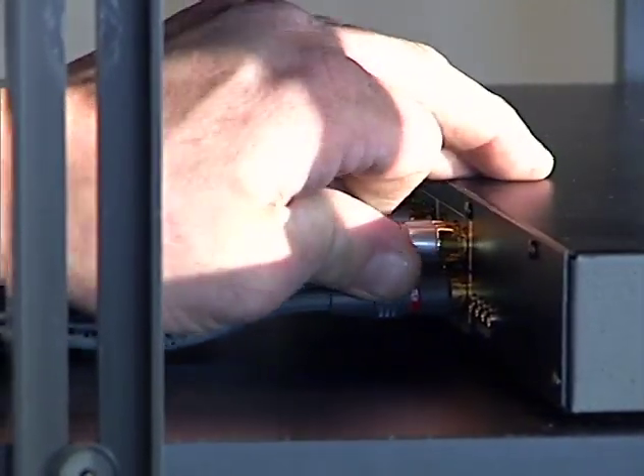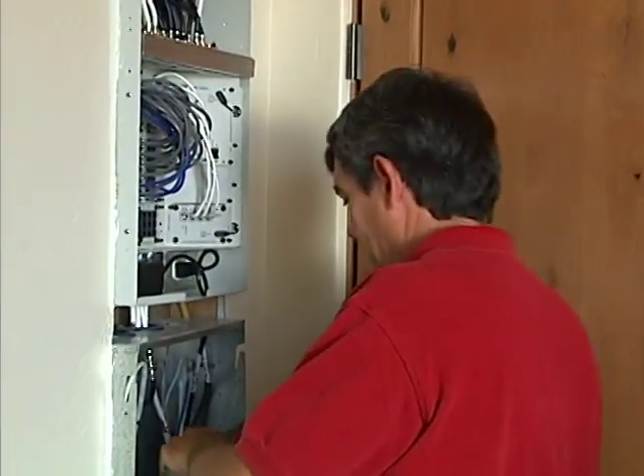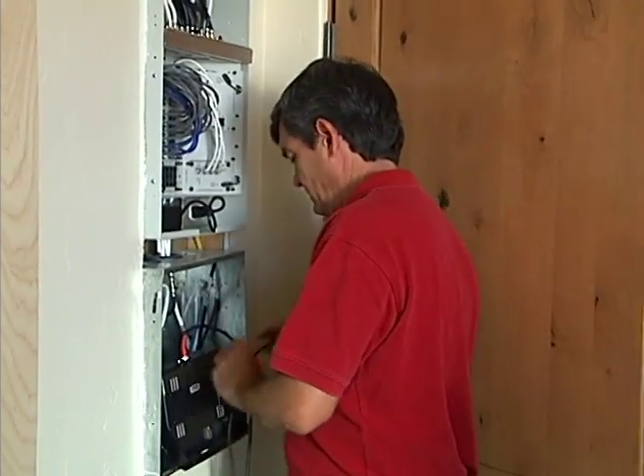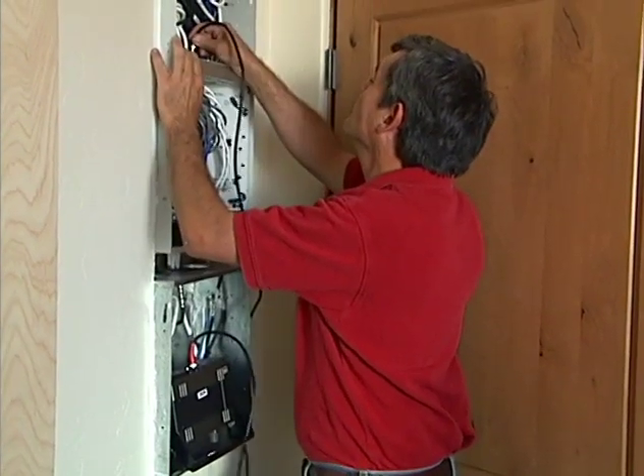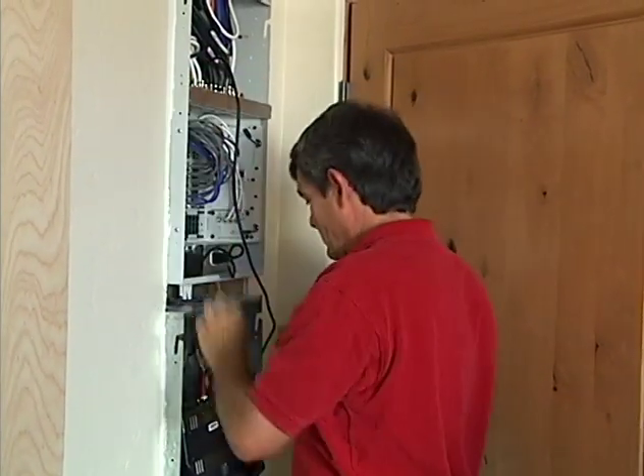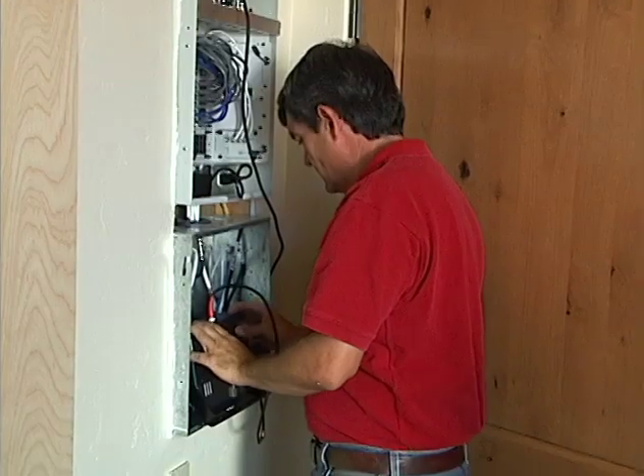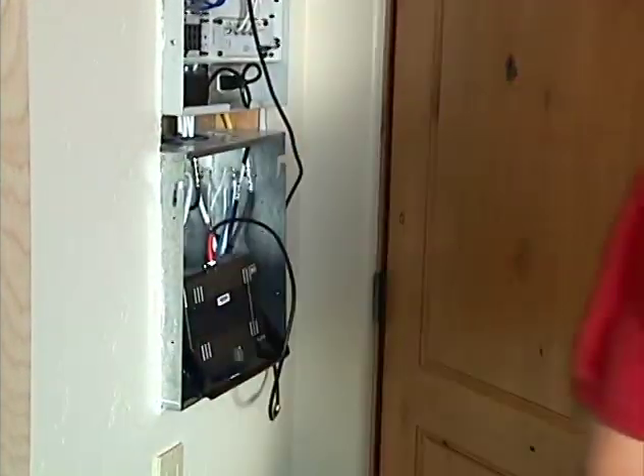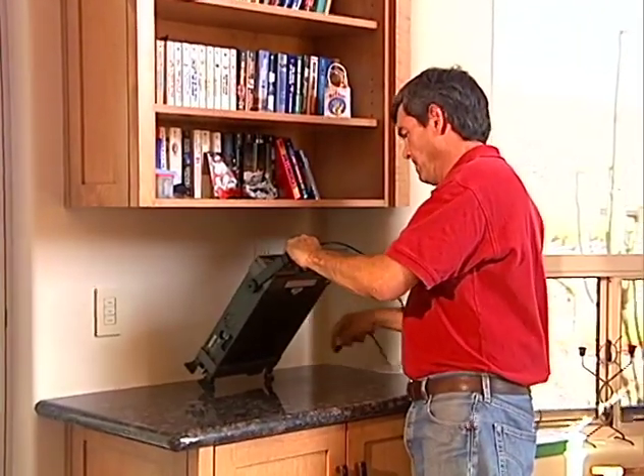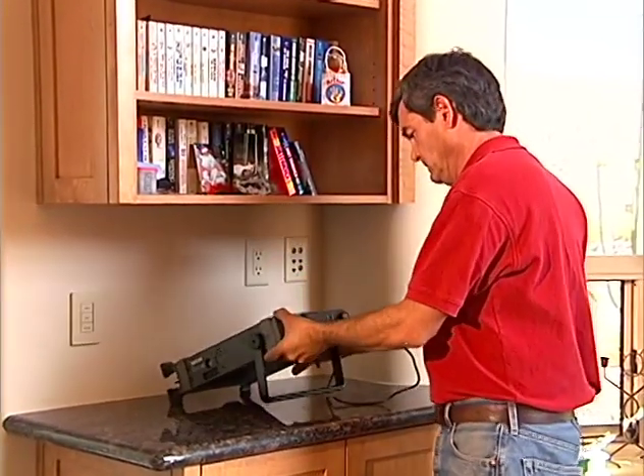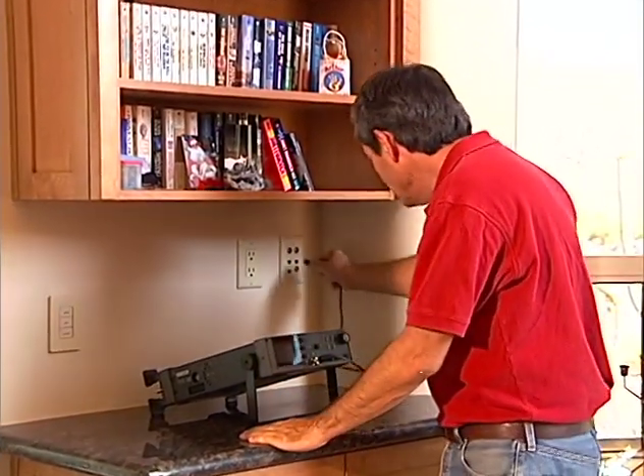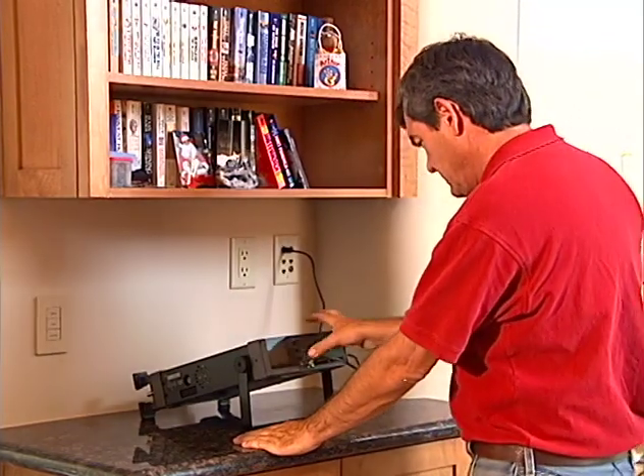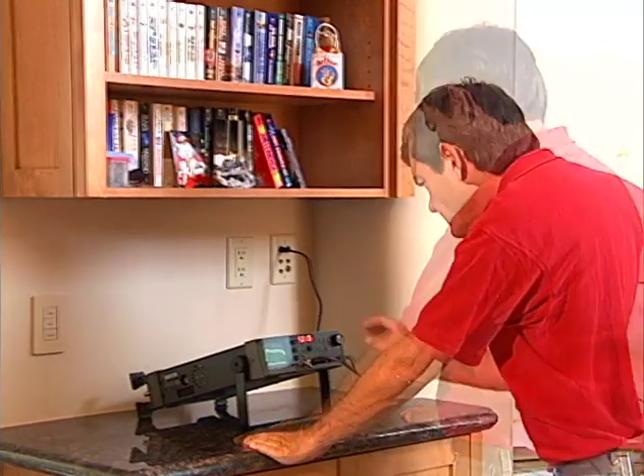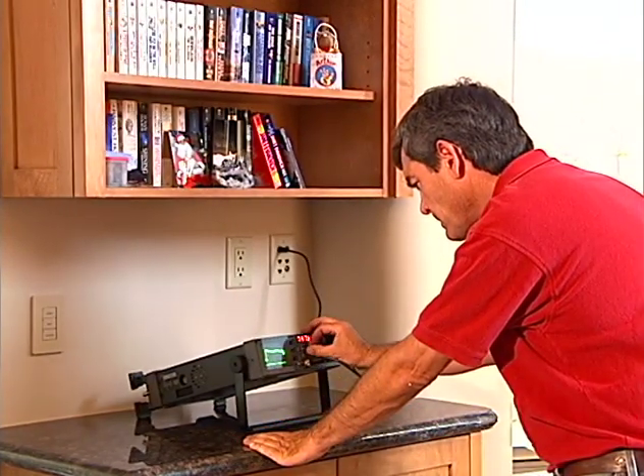While they're finishing the entertainment center, I prepare to do a final performance check of the RF distribution system. I attach a broadband RF noise generator to the off-air input without the filter and set the output level to 0 dBmV. I attach the spectrum analyzer at the outlet with the worst case loss, and set the analyzer to display 0 to 950 MHz.